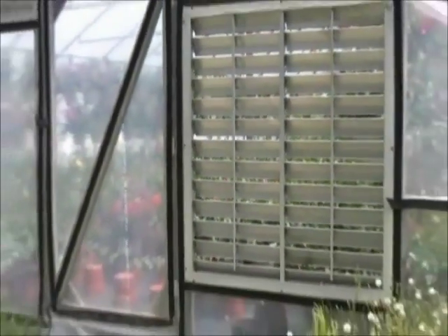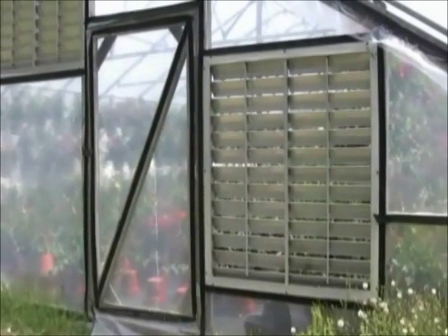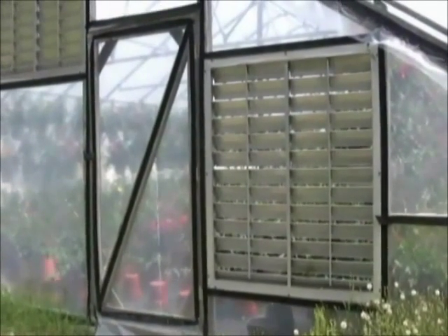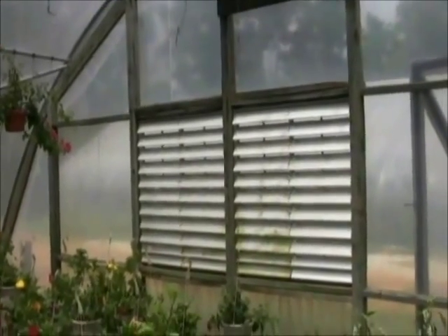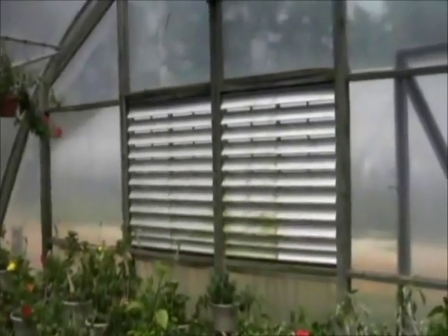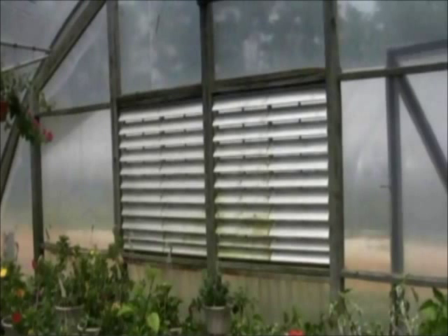As the hot air is drawn out of the greenhouse by the fans, a slight vacuum is created that causes outside air to come into the greenhouse. This combination of exhausting hot air and bringing in cooler outside air can serve as an effective way to lower the greenhouse temperature. However, the best you can expect from this type of fan and vent ventilation system is to lower the inside temperature of the greenhouse during the day to close to the same level as the outside air temperature.